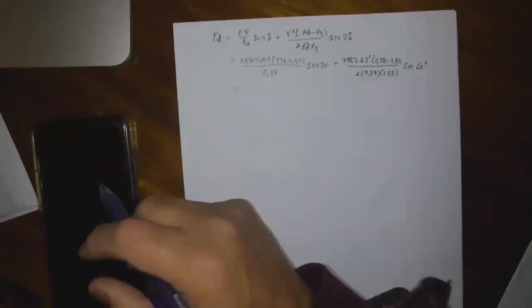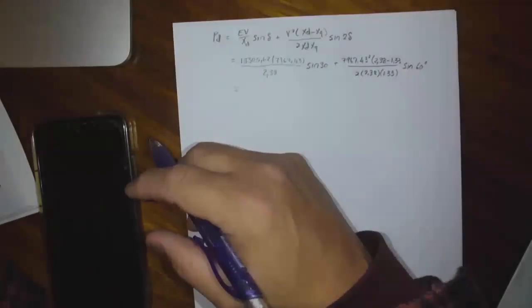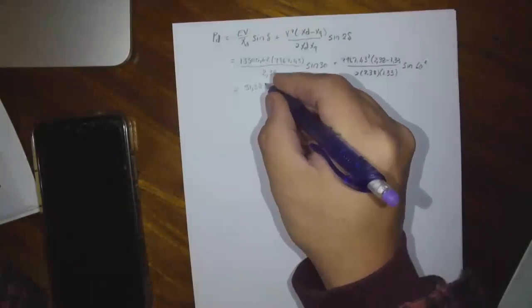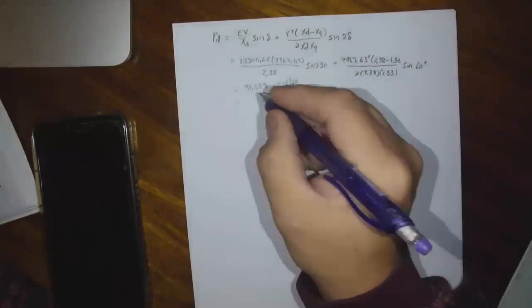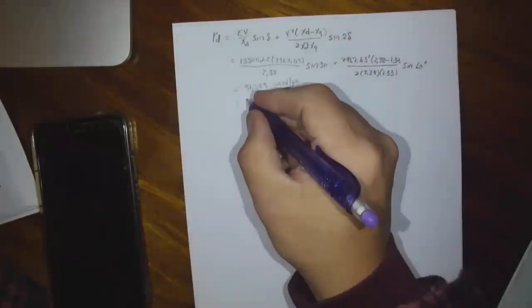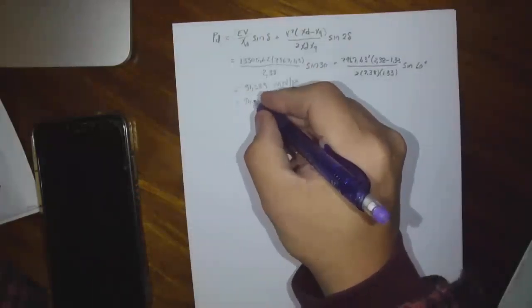Okay. I've got no problem with that, as long as it's right. So how do you get that answer? Okay, it's per phase. It's 31.389 megawatt per phase. And that is total? Yes, multiply by 3, it's 94.168.